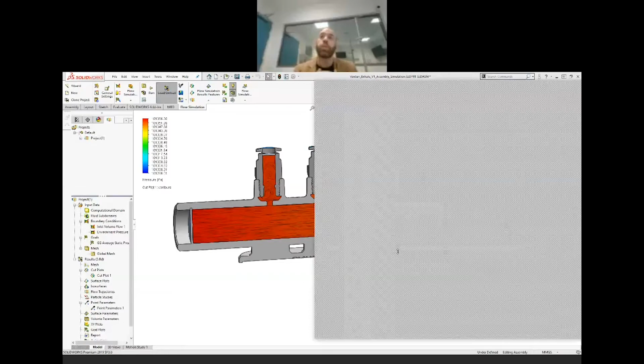So from there, this is typically how a ventilator works. It will monitor the pressure, it will monitor the flow. We talked about pressure control, we talked about volume control. To be able to reach those controls and reach them properly, we need to be able to measure it, because there are plenty of designs that estimate it. They estimate that this is how much volume that we're putting into the patient.